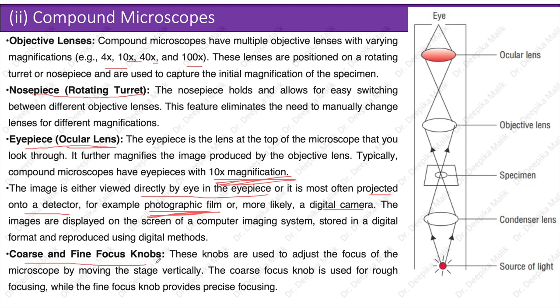Coarse and fine focus knobs adjust the focus by moving the stage vertically: the coarse focus knob is used for rough focusing, while the fine focus knob provides precise focusing. The light path goes from the light source through the diaphragm to the condenser lens, which condenses the light onto the specimen. From the specimen, light enters the objective lens, which magnifies the image, and from there passes to the eyepiece or ocular lens for further magnification before being viewed by the eye.